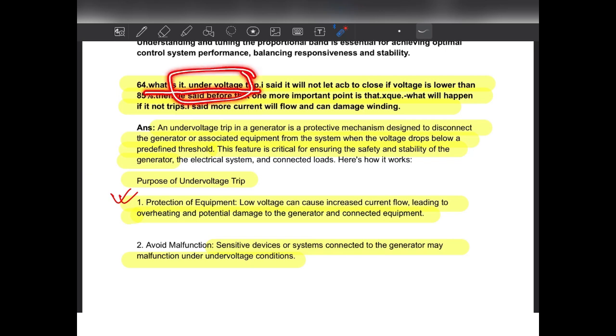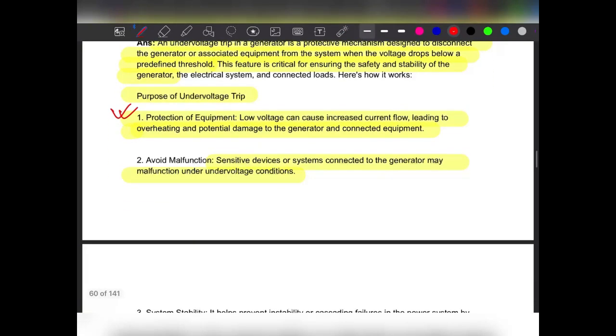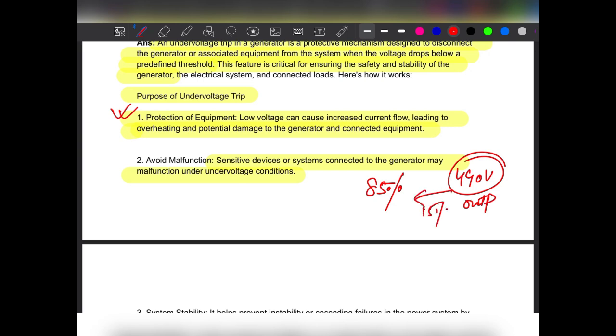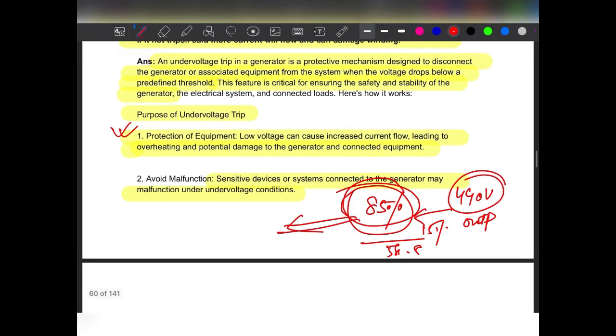Okay, the under voltage trip basically senses the under voltage of the generator. If the generator voltage falls, let's suppose in our ship vessel to 85% of the voltage, let's suppose 440 volts is the full load output voltage, but if it drops by 15%, down to 85%, and this is the set point of the under voltage relay, and the voltage stays at 85% of the full load voltage for a few seconds, let's say 5 seconds, 8 seconds, then it will sense and give a signal to the relay. It will trip the circuit and isolate the circuit from the bus bar.